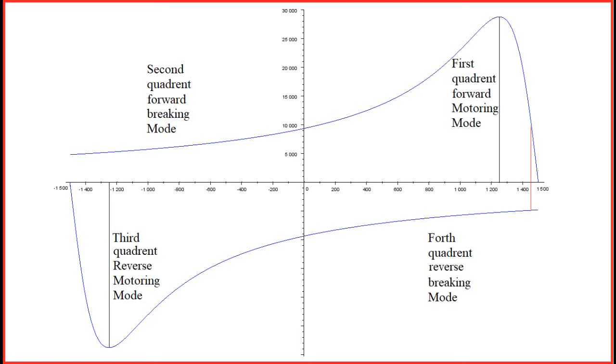This interchange of phases will reverse the direction of rotation of magnetic field. This will also reverse the direction of motoring torque. In this way, motor starts operating in fourth quadrant. Direction and value of motor speed could not change instantaneously. So for example, suppose at instant of applying brake or altering of phases, speed is 1450.